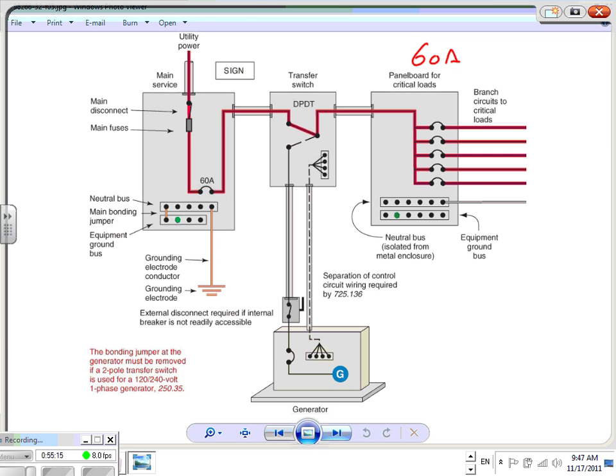Okay, let's follow this one, guys. The equipment neutral bus is isolated from the metal enclosure. I want to bring to your attention that the neutral and the ground are isolated in this case. Now, if this is a three-pole circuit breaker and a 3-pole auto transfer switch, so I'm switching the 2 hots and a neutral, this becomes a separately derived system. Here's how we do a separately derived system.